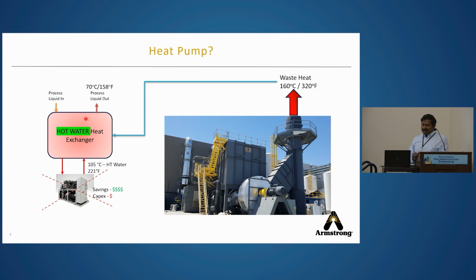In Armstrong, we believe that we want to do the right thing by the customer. So for this particular facility, we would educate the customer to do direct heat recovery instead of going for a high temperature heat pump, even though it is completely funded, but still do not go for it. So how can we identify whether the facility really requires a heat pump? Can they live with direct heat recovery?